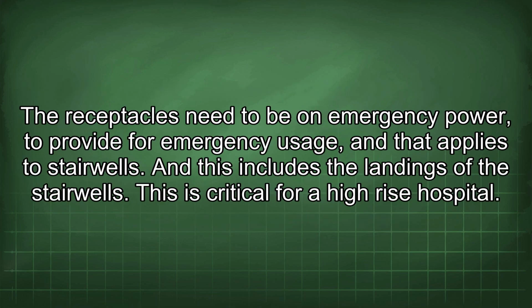The receptacles need to be on emergency power to provide for emergency usage, and that applies to stairwells. And this includes the landings of the stairwells. This is critical for a high-rise hospital.